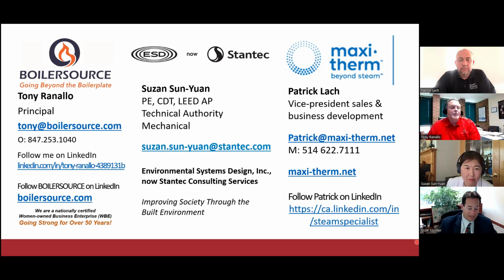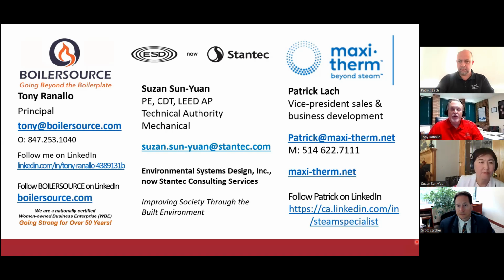That's a great question. And we have plenty of systems like that out there. The key here is to try to maximize all your... I should not maximize, but minimize all of your losses. So if you're doing a steam system that is remote, in either another building or another room, where we have vertical flooded heat exchangers and we're not returning condensate below 130, yeah, you're going to have some savings. Every degree that we can save on our condensate return temperatures has less losses on your condensate return lines.